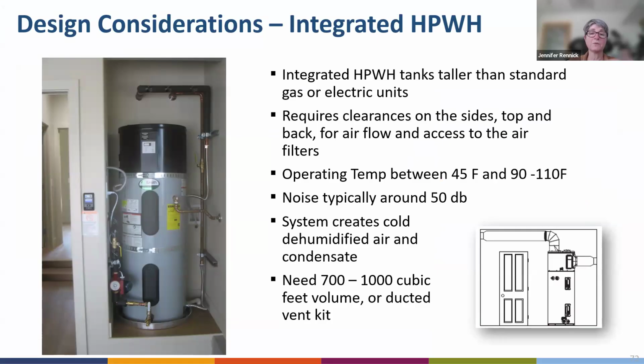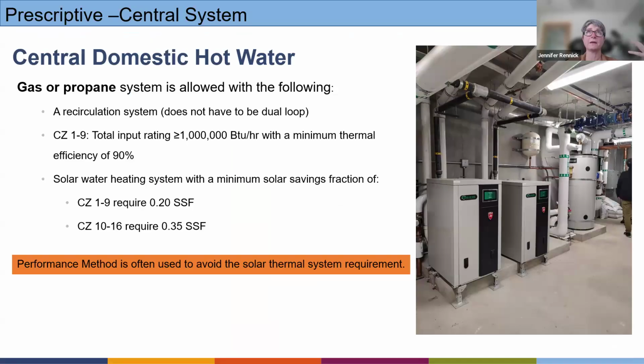There's design considerations with the heat pumps we alluded to. This is a lot of good rules of thumb that I like to remind the designers when they're looking at locating these heat pumps. However, now with those mandatory measures, a lot of these requirements are baked in, other than understanding that the noise is typically around 45 to 50 decibels. So how you design for it in a small apartment can be important. A lot of times we'll see them in exterior closets where the closet's open to a balcony, and that closet has a buffer. That way the closet's exterior to the dwelling to help cut down on noise, etc.